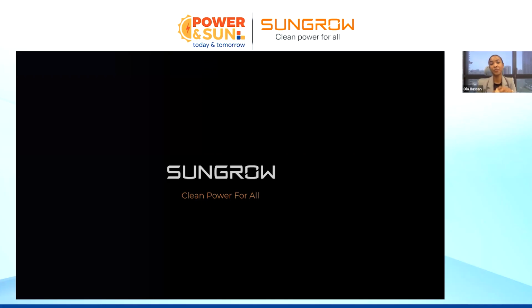Okay, so the emergency load, Vijay, is actually based on the hybrid inverters, because the hybrid inverter itself has two outputs: on-grid and backup port, or emergency backup port. In this case, the emergency backup port has the same rated capacity as the inverter. So if my inverter is 125 kilowatt, then the backup port itself can inject up to 125 kilowatt. Yes, that will be the capacity that we can connect at the emergency load. But in case your system is fully off-grid, Vijay, this is a suggestion I always tell our customers and partners: make sure whatever you connect on the emergency load is equivalent or smaller, preferably slightly smaller, than the inverter capacity. Because in this case, the inverter will carry the full load by itself. There is no grid.